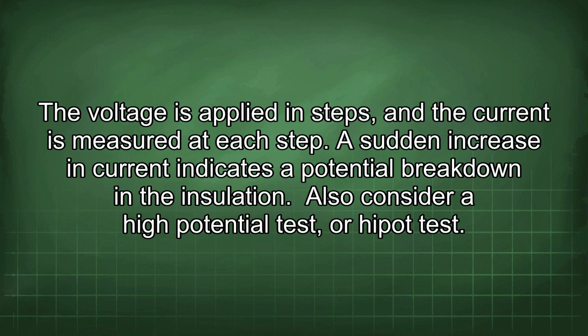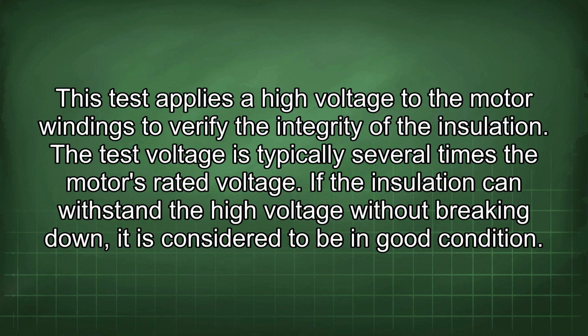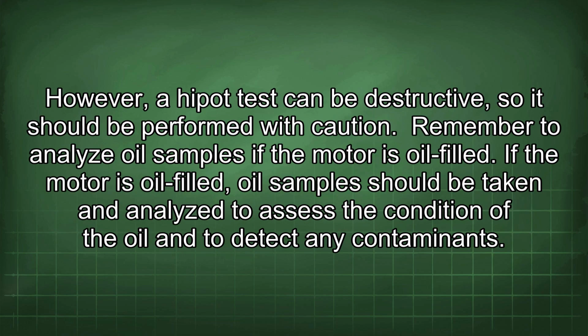Also consider a high potential test, or HiPot test. This test applies a high voltage to the motor windings to verify the integrity of the insulation. The test voltage is typically several times the motor's rated voltage. If the insulation can withstand the high voltage without breaking down, it is considered to be in good condition. However, a HiPot test can be destructive, so it should be performed with caution.